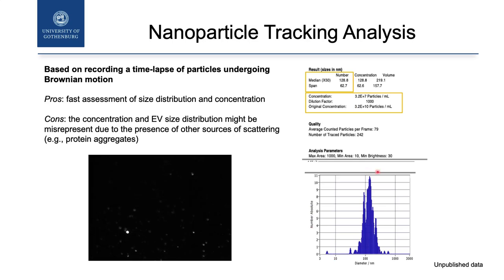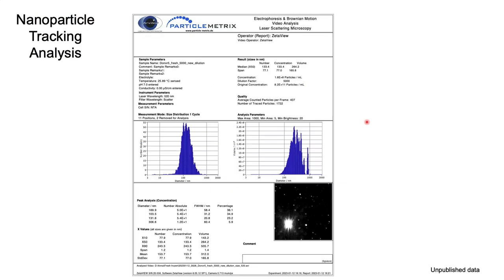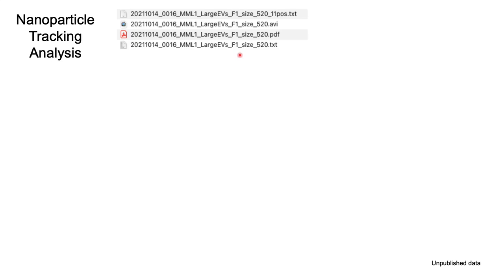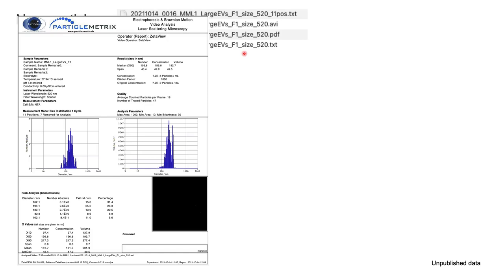You also have the distribution of the particle size. Most of us are happy when we get these numbers and can use them for the rest of the experiment. But the message is that we can get much more information from this machine. This is the entire PDF file that you get — you can already notice something strange here, probably an aggregate or something that the machine doesn't count. You get four or five files from the machine and I want to tell you: if you have time, look at all the files the machine gives you.